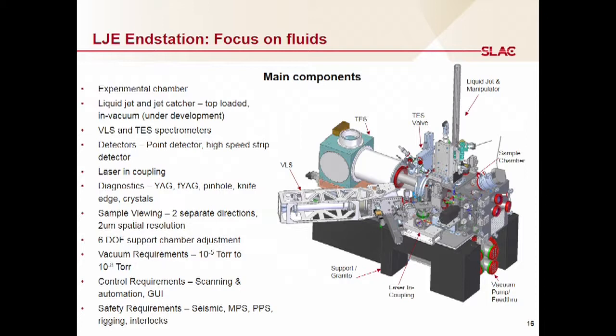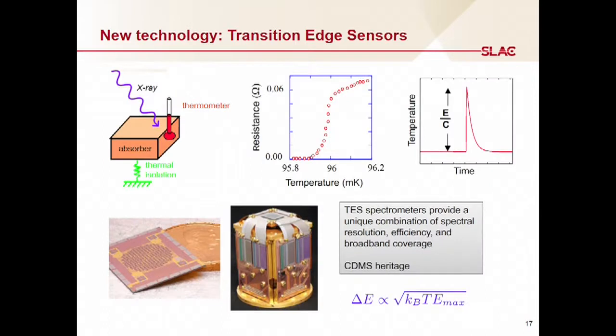And we have a few X-ray emission spectrometers that can tell us what's the energy coming out. We're actually quite excited about the development of a new type of spectrometer. It's not this grating spectrometer that I mentioned earlier, but it's based on these transition edge sensors, which are really tiny elements. They're about the size of a penny here, but they're cooled down to a very, very low temperature, and they're superconducting. So if they absorb light, they go into their normal state. So this jump in resistance tells us exactly what their photon energy is. So it's a new technology, it's rapidly developing, and we're quite excited to see how it can be applied for our cases.